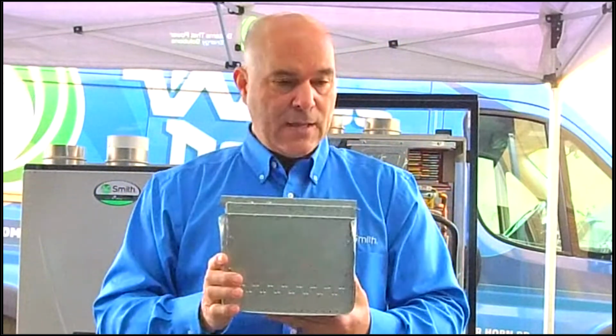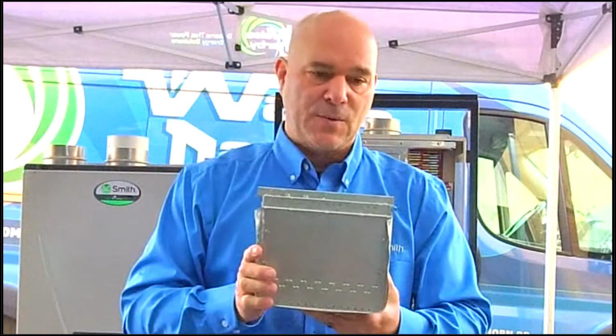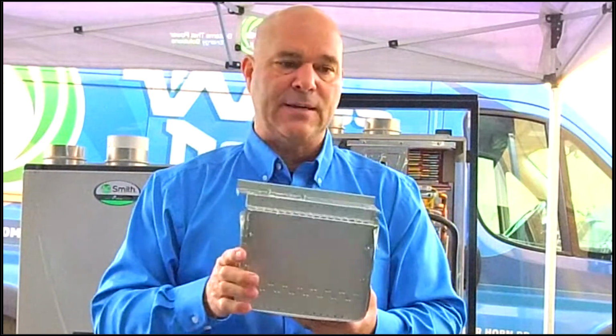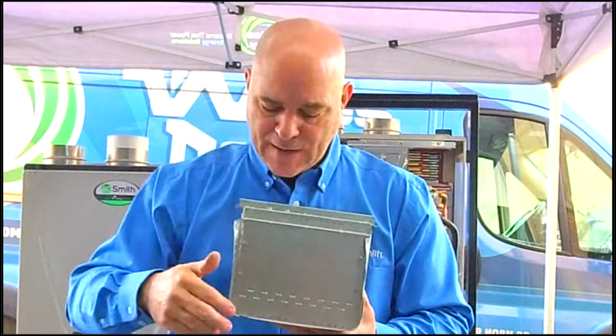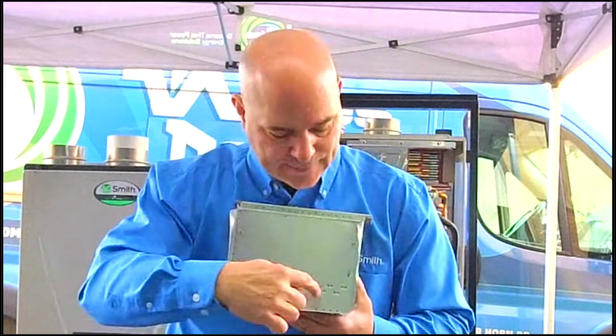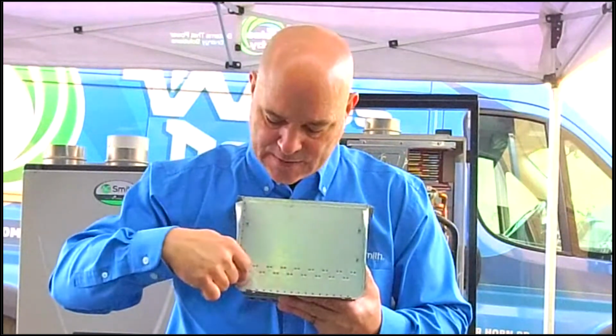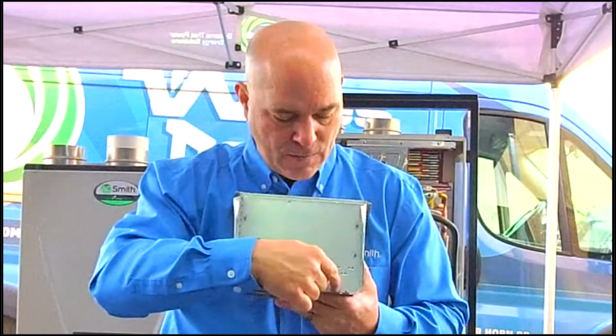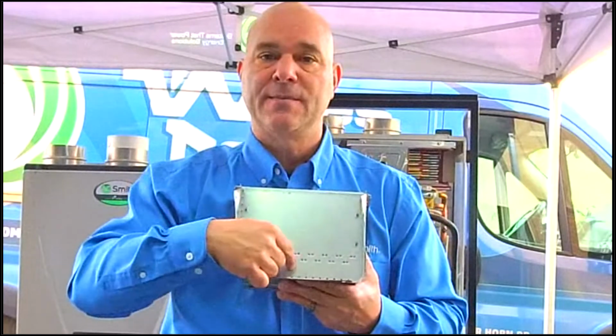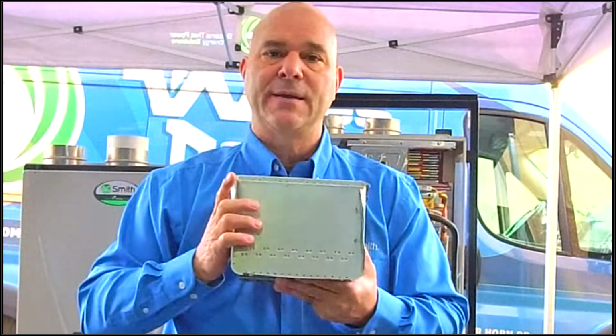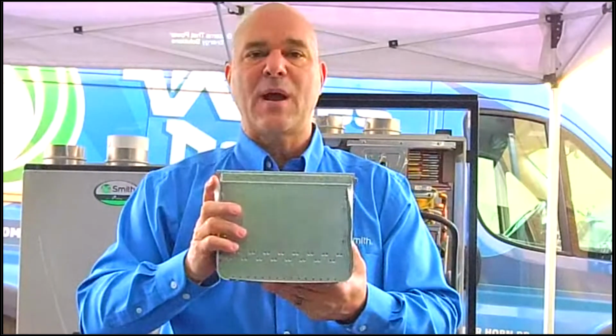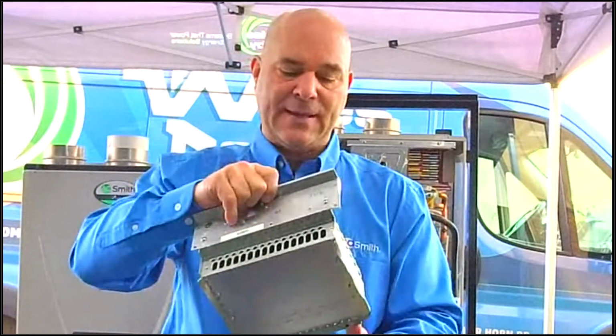If you're in the field and you have a unit that's in a dusty situation, or there's sheetrock dust in the room, and you have to pull this burner tray out to clean it, it's critically important to clean all of these air holes around the burner tray. You want to make sure that whole area is clean so that you get proper combustion when you put it back together.